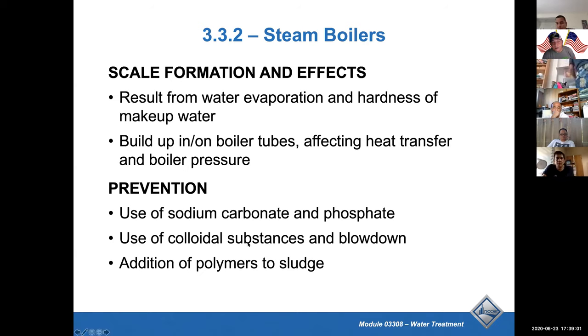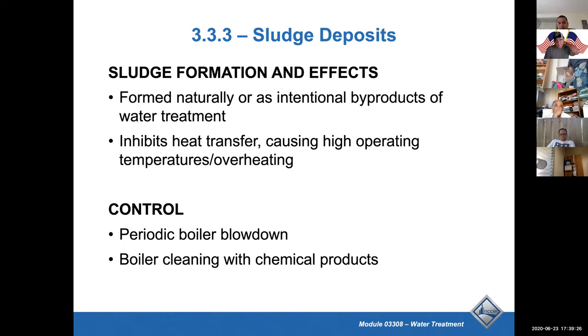Use a colloidal substance, which makes the suspended solids fluid, so you can blow it down when you do your blowdowns. Addition of polymers makes it flow better and it doesn't adhere to surfaces. That's what the polymers on the bottom there are. Sludge formation happens in dead areas of a heat exchanger or a boiler. Blowdowns help that, and mechanical cleaning also helps.